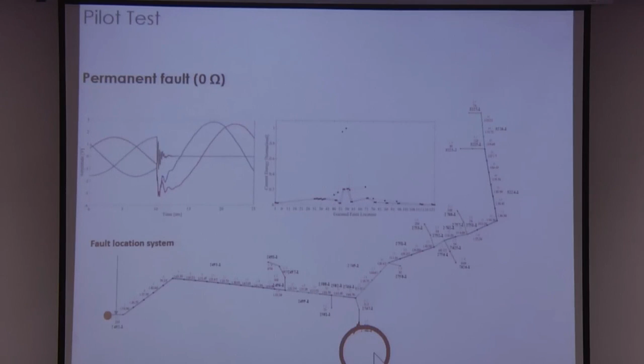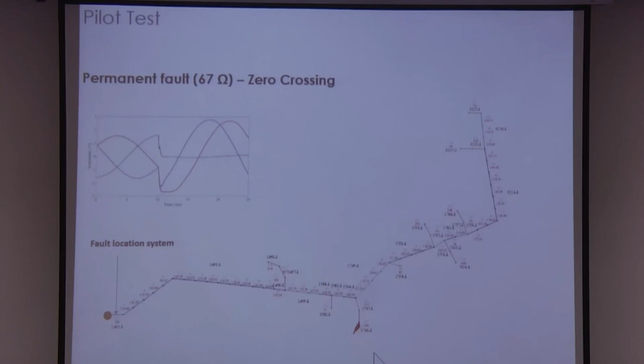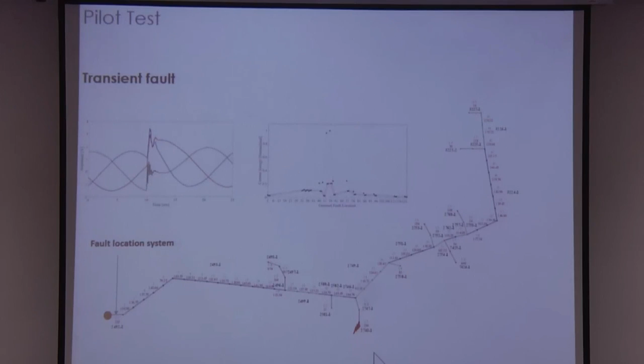Then with the zero crossing, because traveling wave-based methods might suffer when the fault happens at the zero crossing, the method, fortunately, worked without any problem. For high impedance faults, we increased the fault impedance to 67 ohms. Again, we were able to find it. And finally, for a transient fault, not a permanent fault, we were also successful in this test.